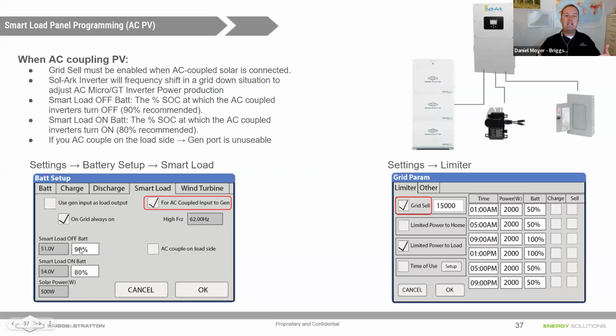We don't want to wait until we're completely full. As soon as the batteries drop below 80%, we let the AC coupled solar start charging again, leaving a little differential so it's not flipping on and off. That's where grid sell comes in—where we limit the amount of power we sell back to the grid, and that's where the NEC's 120% rule comes into play.